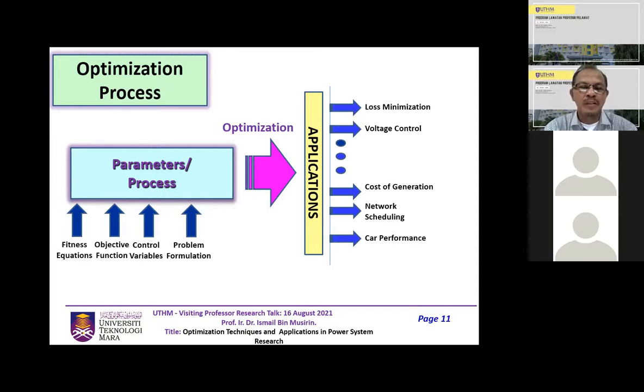So basically, let's say you've got 100 kV. The minimum voltage which is considered secure is 95 kilovolt, and the maximum one is 105 kilovolt. That is considered within the working limit, which is 0.95 or 95% to 105% of the nominal voltage. So what happens is, let's say your voltage is going down below 95% of the nominal voltage, so you are going to get V1 angle delta 1 minus V2 angle delta 2 divided by Z. So when V2 is going down to a low level, we are going to get an increment of current. So I goes up.